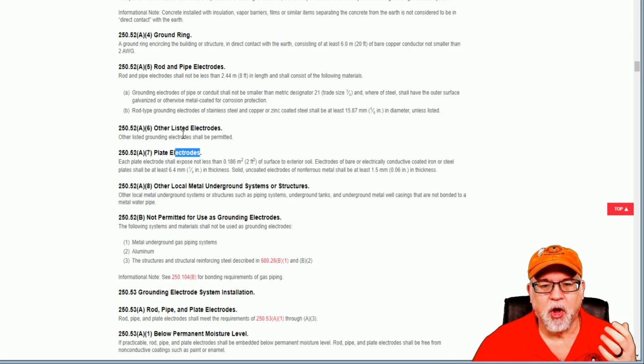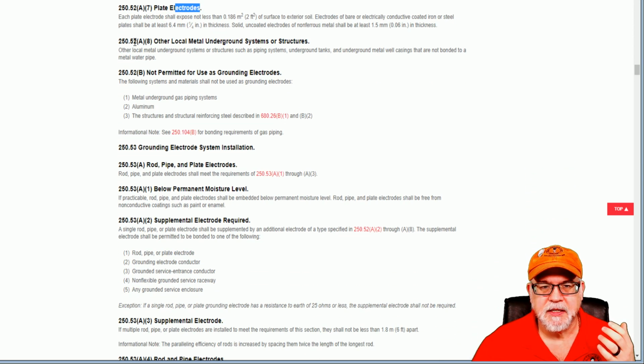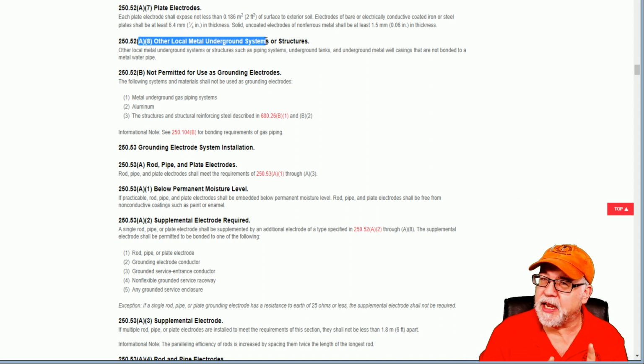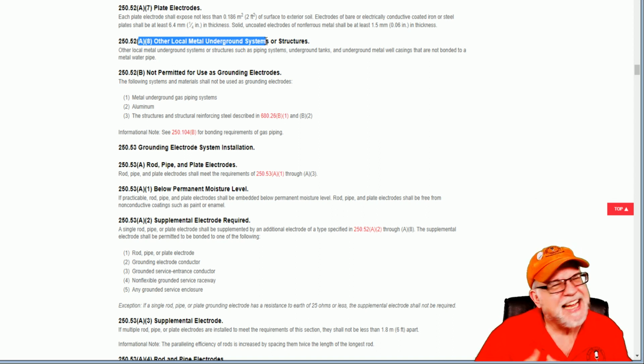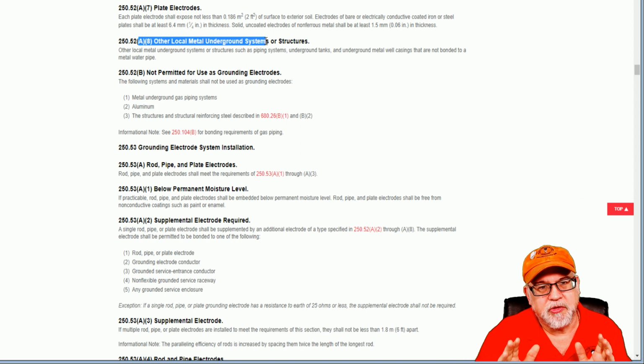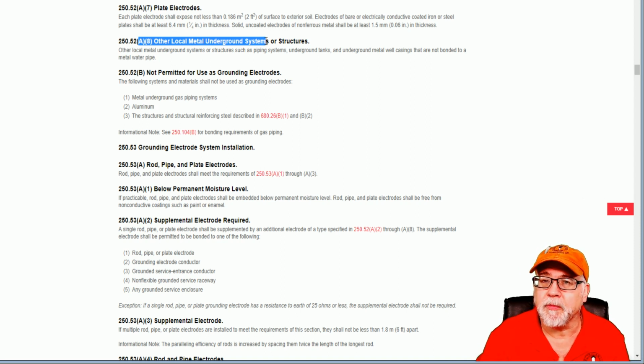All right, so you have all those, and of course, here's your A8, other local underground system. Now, check with your AHJ here, because you might have an underground tank, but they don't feel comfortable with that as an electrode to make a connection, or maybe a well casing. They can't see it. They don't know anything about it, so they're probably going to say, I don't know. You're not going to use that. But the others are all there for your use, and if they're all there, they all have to be tied together.